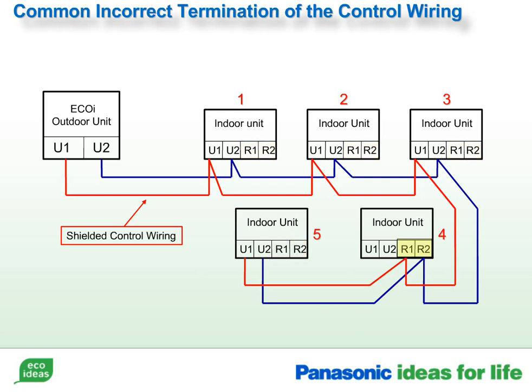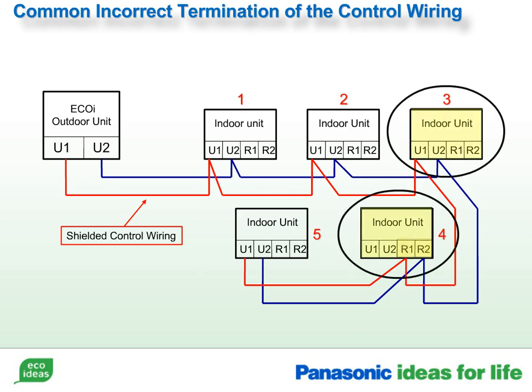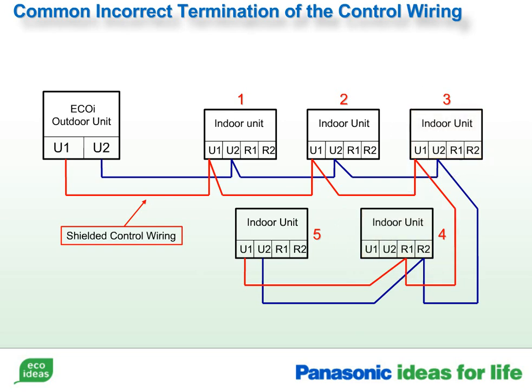If your outdoor unit was set to 5 indoor units, as in this example, it would only see 3 units, and you would get an error code. If you lowered the outdoor unit settings to find 3 indoor units and no error codes are reported, then you would know the problem was between the 3rd and 4th indoor unit.